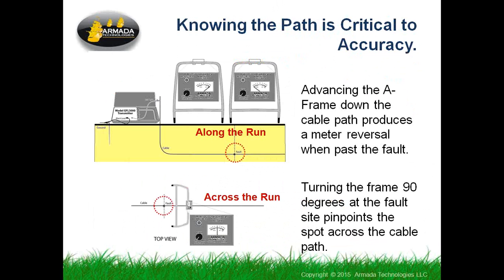So back to this issue of knowing the path: you have to have the path, because as we are searching for faults, we begin by going along the cable run. We're going laterally down the cable until we find a place where the ripples in the ground reverse and we're over the top of the fault. Then secondly, we go across the run with our A-frame to make sure that the fault is directly crossways on the cable using the same kind of meter indications. When we've done this, I often tell people what we've done is found the fault within one shovel width.